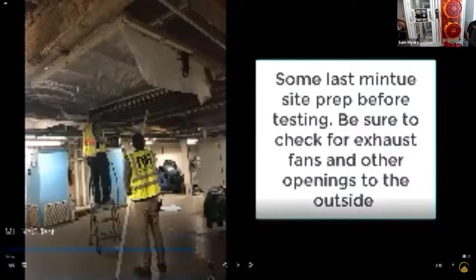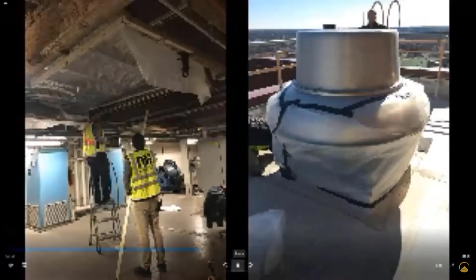Unfortunately, there wasn't really good communication between the testing team and the building operators or engineers, so there wasn't as much prep work done as needed. There were big louvers in the elevator penthouse that we had to go up and seal off - you can see this roll of plastic, and we had to screw in some 2x4s to keep it sealed. Otherwise we wouldn't have been able to get the building under pressure. There were also several of these mushroom cap exhaust fans up on the roof that we had to get taped off. So a lot of plastic, a lot of tape to get these things sealed.